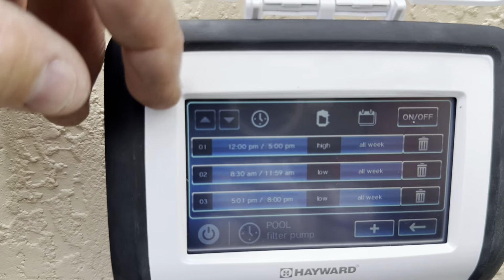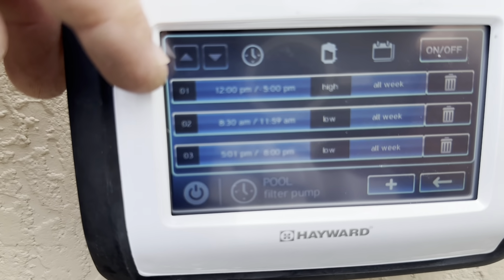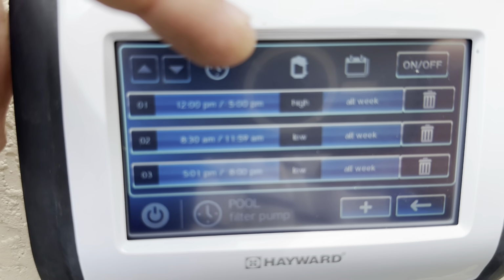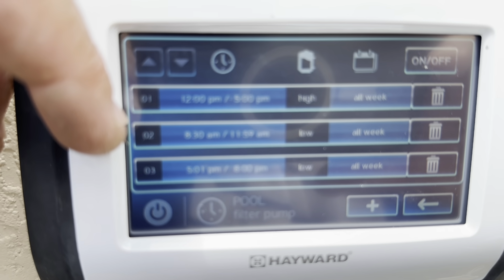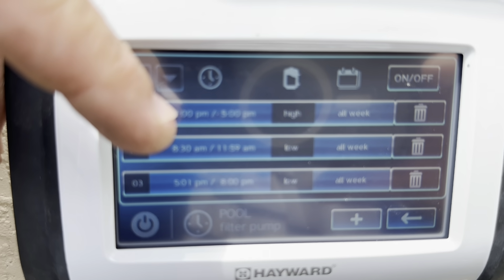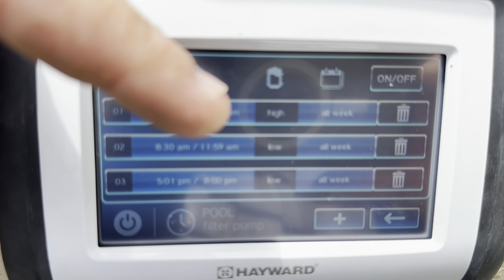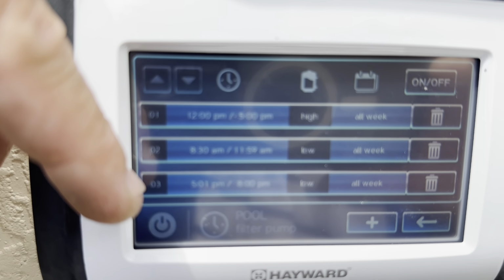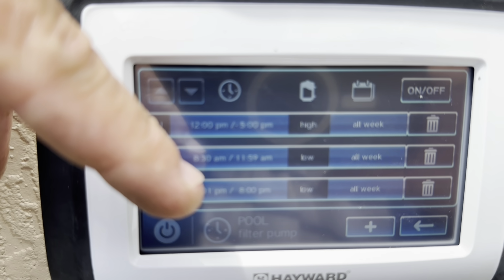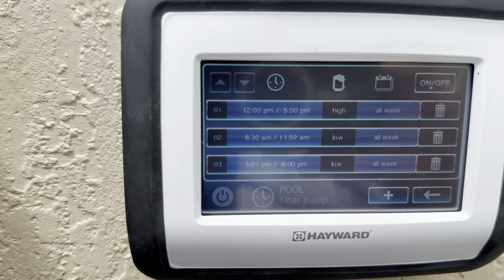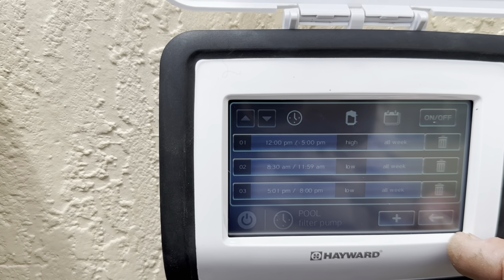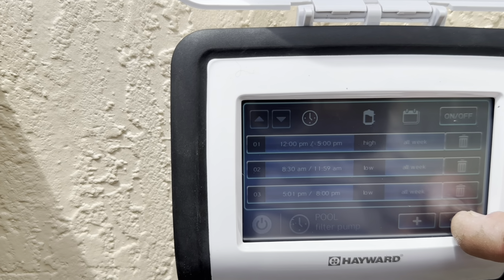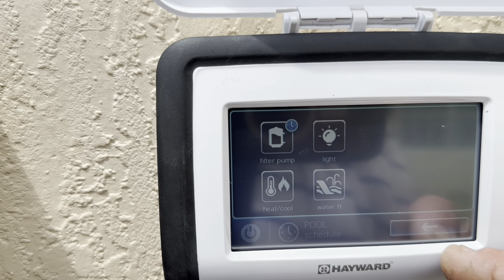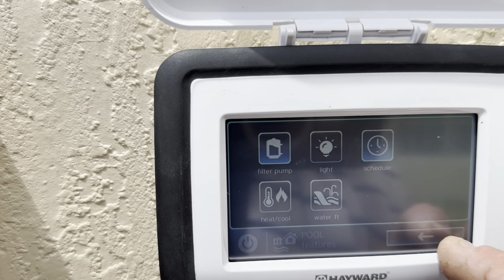So I've got my high speed coming on at 12 p.m. to 5 p.m. all week. Then I've got my low speed from 8:30 a.m. to 11:59 a.m. all week, and another low speed setting from 5:01 p.m. to 8 p.m. That's going to do it there, so that sets that up.